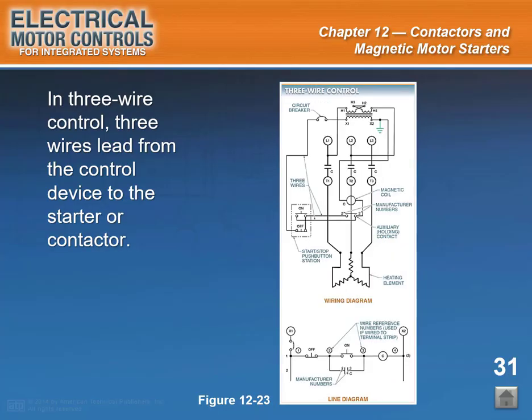Slide caption: in three-wire control, three wires lead from the control device to the starter or contactor. See Figure 12-23. The circuit uses a momentary contact OFF push button, normally closed, wired in series with a momentary contact ON push button, normally open, wired in parallel to a set of contacts that form a holding circuit interlock or memory. End of slide 31.